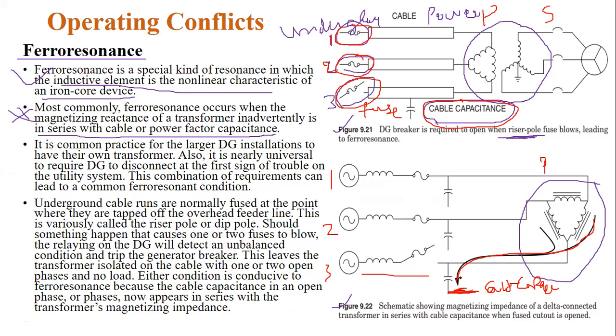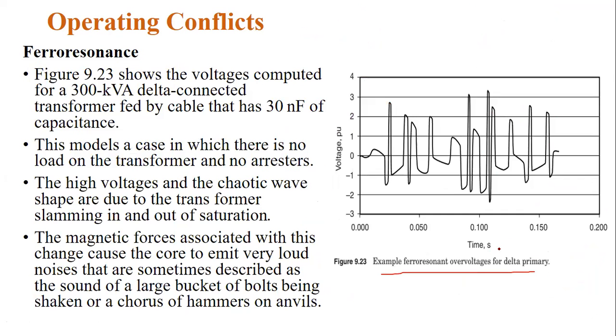Okay, now see this. Whether any one of the fuses is blown, in that case, how do the transformer voltage waveforms appear in this diagram? This is the time in this case. This is the voltage we can measure in per unit values. That may be 230 volts, that may be 440 volts, a 132 kV system, or whatever. Here in this case, a 300 kVA system transformer they can consider. Then what is the cable capacitance here? They can assume here 30 nanofarads.